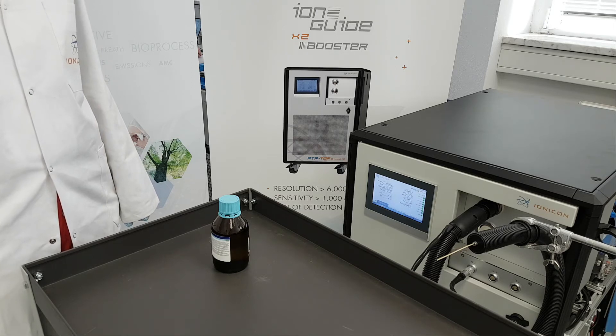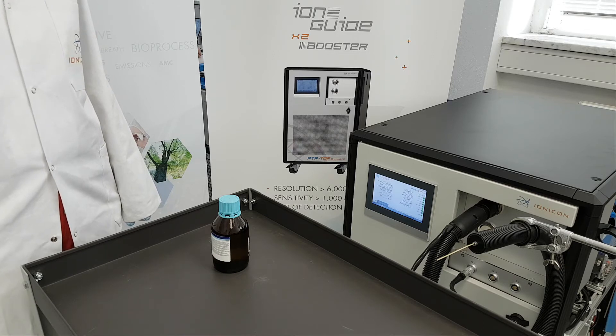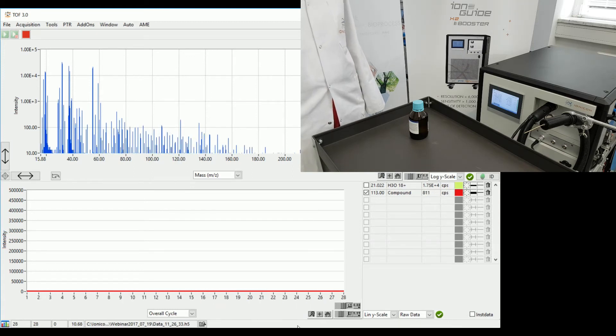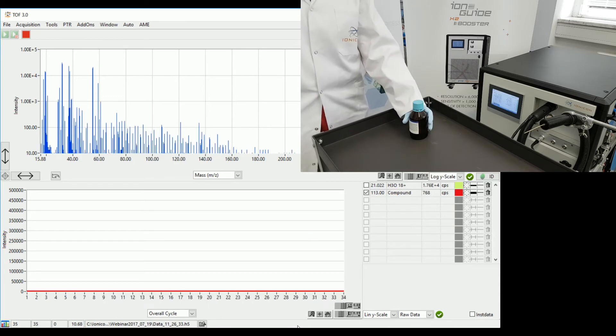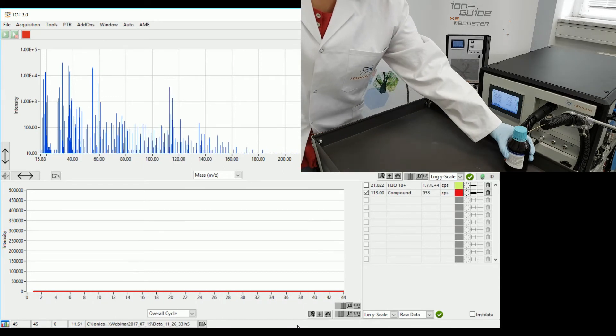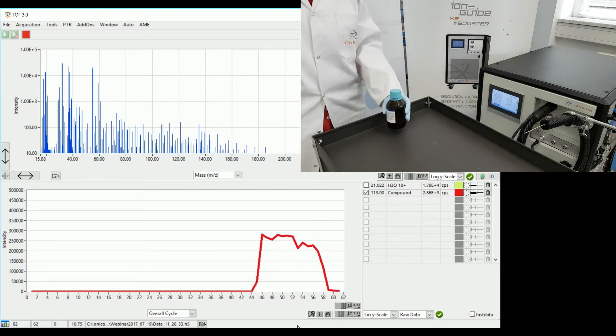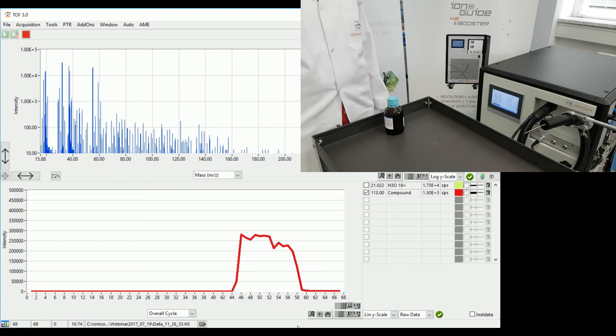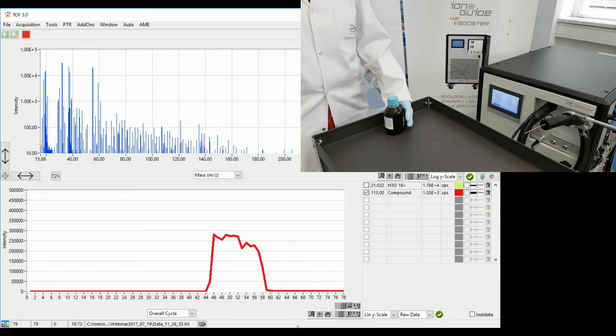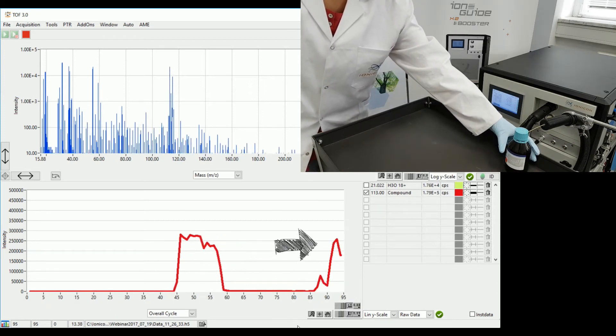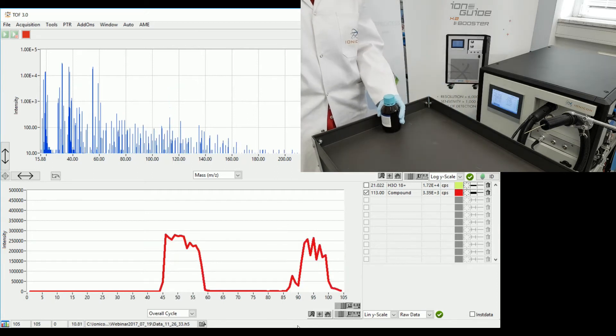For the lab experiment, I use a closed bottle bought from a chemical company as a sample. Before I put the bottle in front of the inlet system, the PTRMS is measuring ambient lab air as a background. When I place the bottle in front of the inlet system, the signal rises immediately within milliseconds. When I remove the bottle, the signal decreases to background level within milliseconds again. Again you see the immediate response of the system and the immediate decrease after removing the bottle.